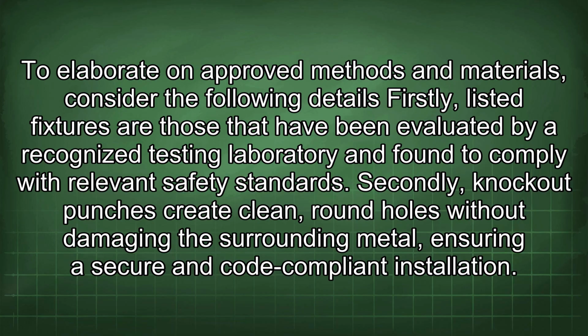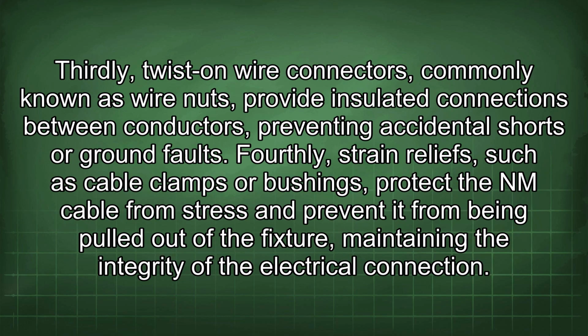To elaborate on approved methods and materials, consider the following details. Firstly, listed fixtures are those that have been evaluated by a recognized testing laboratory and found to comply with relevant safety standards. Secondly, knockout punches create clean, round holes without damaging the surrounding metal, ensuring a secure and code-compliant installation. Thirdly, twist-on wire connectors, commonly known as wire nuts, provide insulated connections between conductors, preventing accidental shorts or ground faults.